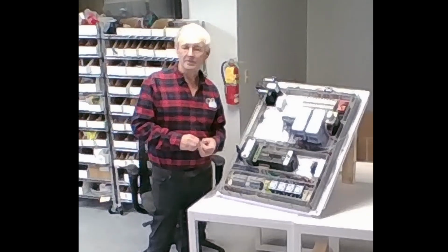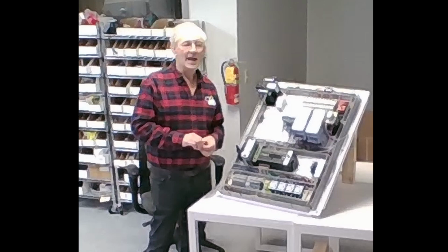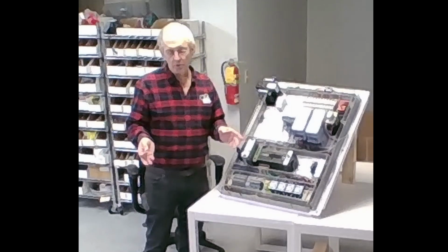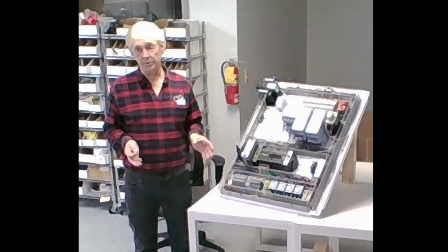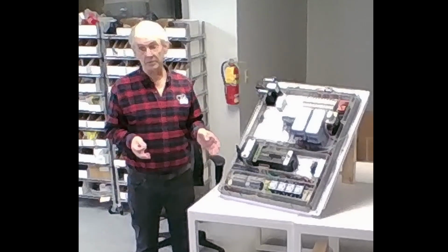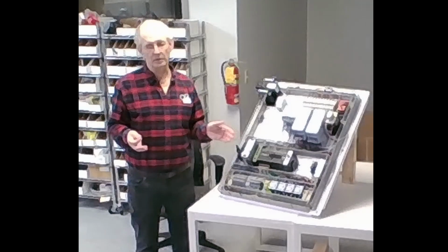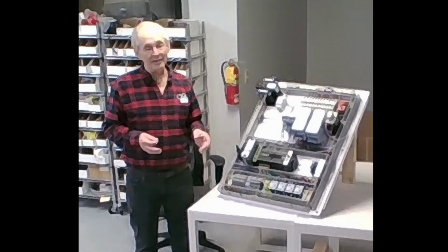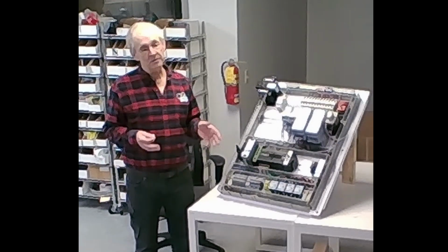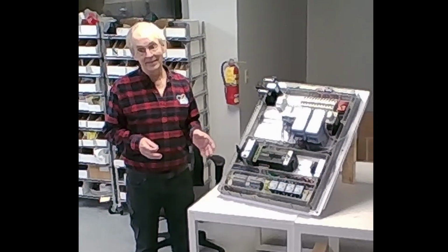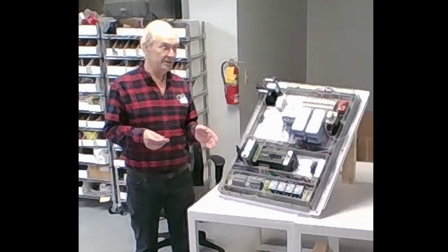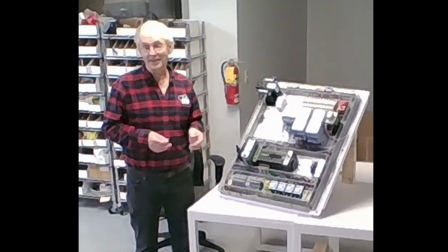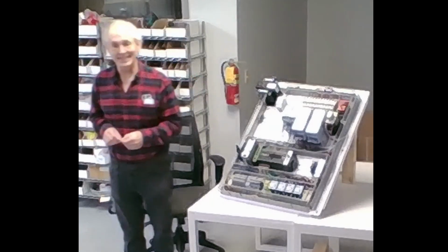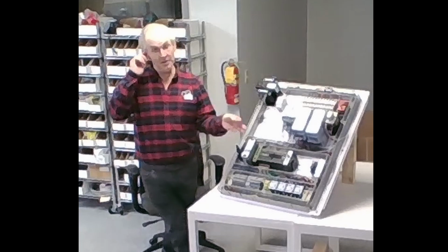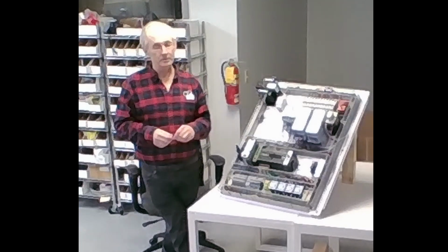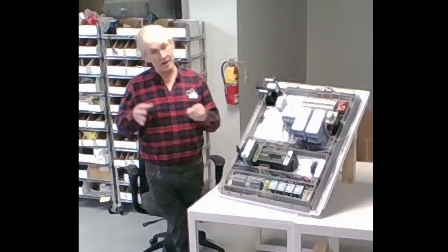And in the case of a car wash, motors have what's called service duty factor, right? And three-phase motors have incredible overload capability. This is why your Tesla can accelerate like a rocket. It's because the motor in a Tesla might only be 100, 120 horsepower. But a 120 horsepower three-phase motor can put out over 600 horsepower for short periods of time. What's a short period of time? Well, in the case of a Tesla, it's getting to 65 in 2 seconds flat. That's nothing, right? That's trivial. I mean, in industry, three-phase motors can be overloaded for a minute or two without a problem, as long as it's not continuous.